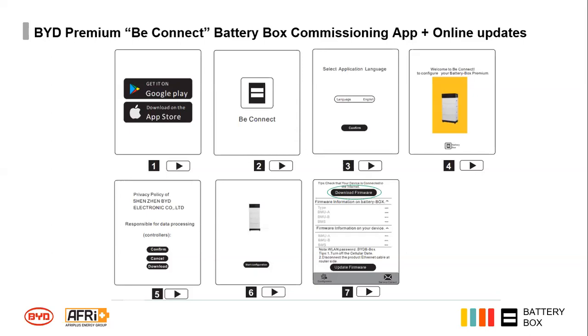The other nice thing about the new battery range is they've got dual processors in them. The advantage of this is you can update the firmware without having to turn the battery off. So when the firmware updates, one of the processors turns off and updates while the other one keeps functioning. When one is updated, that updated one turns on and the other one turns off and updates. So it means you don't have to turn anything off in order to do firmware updates.